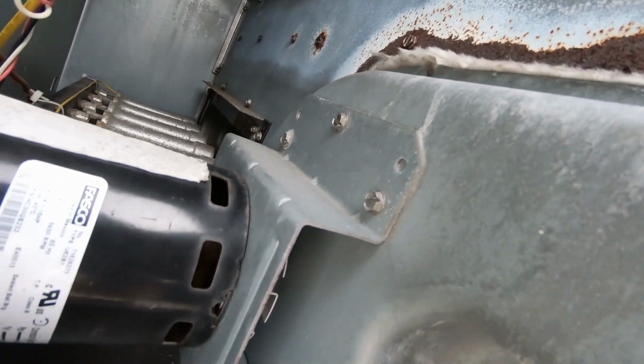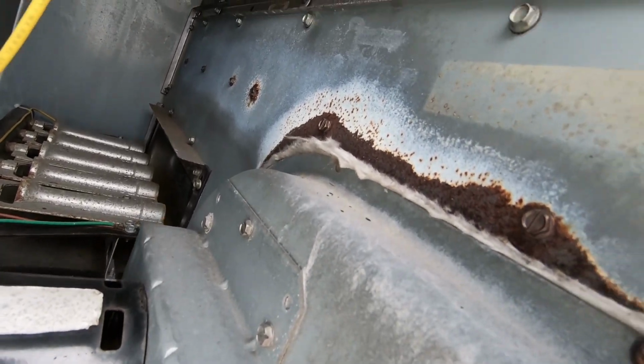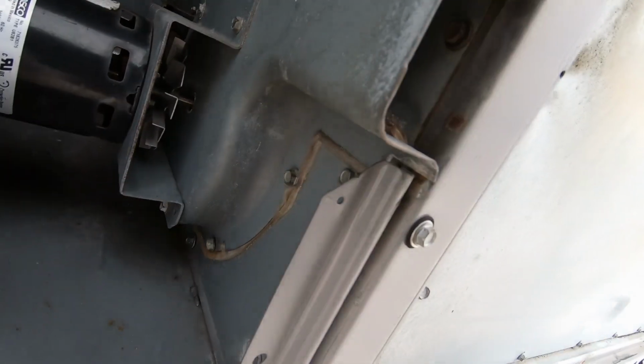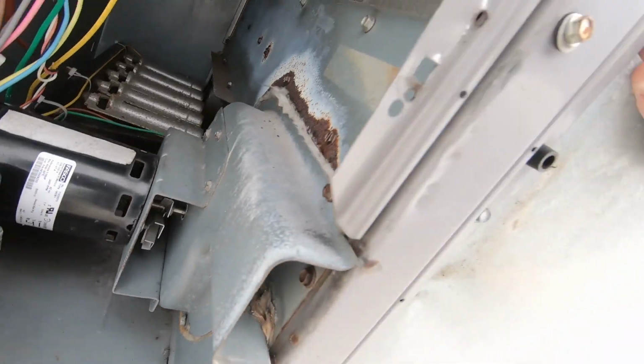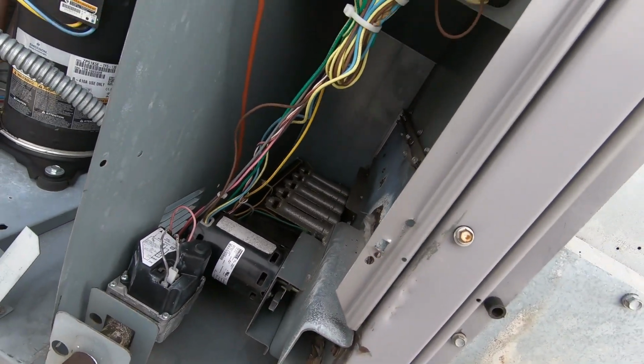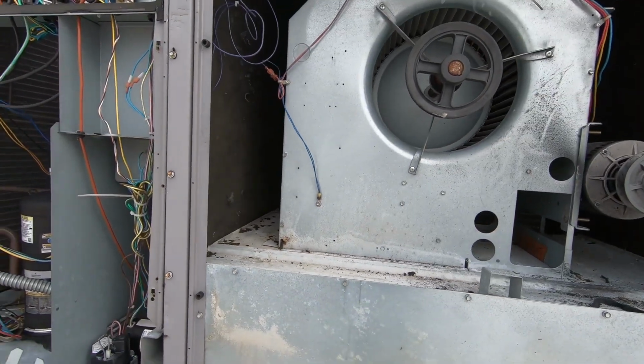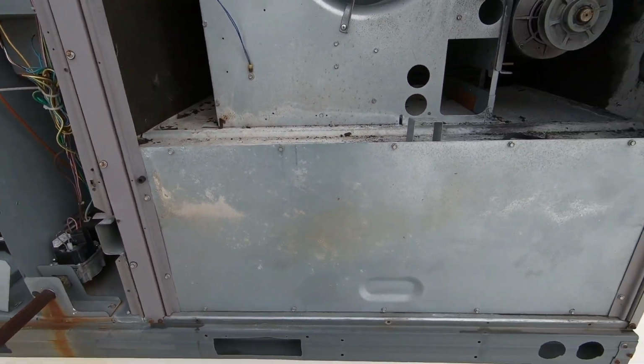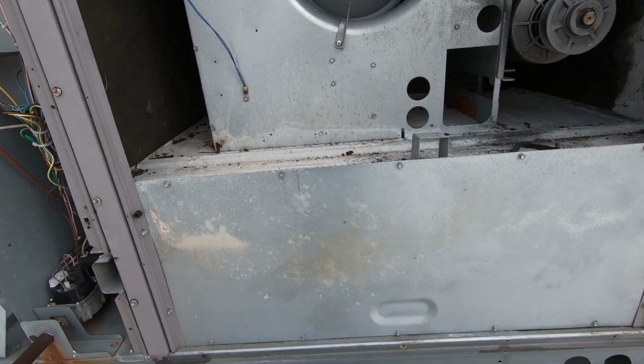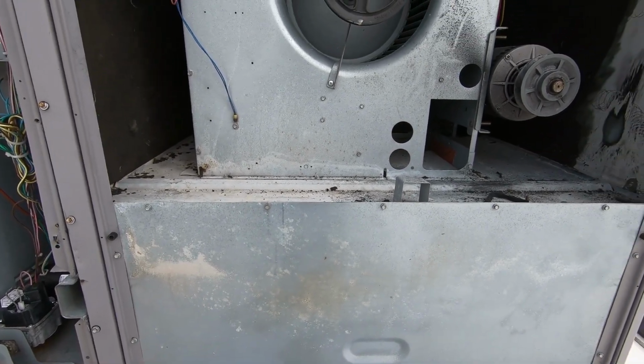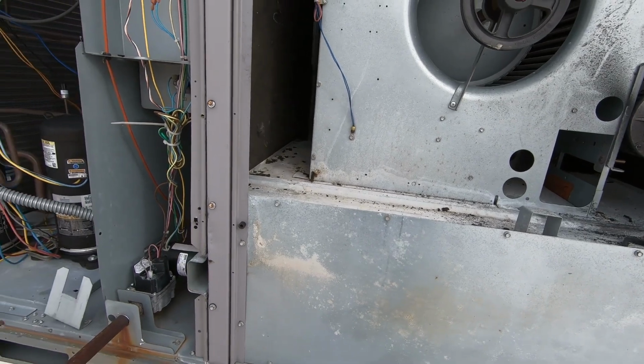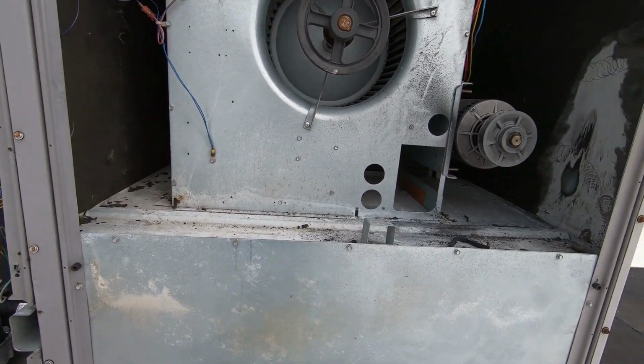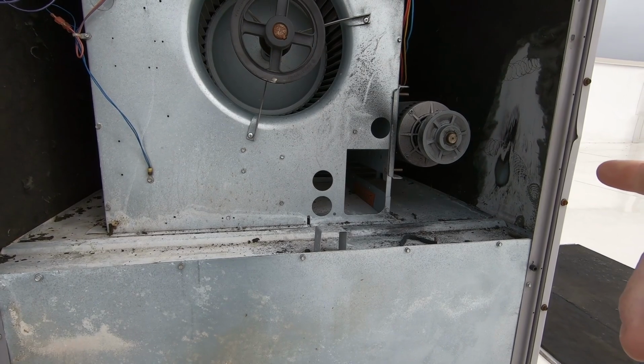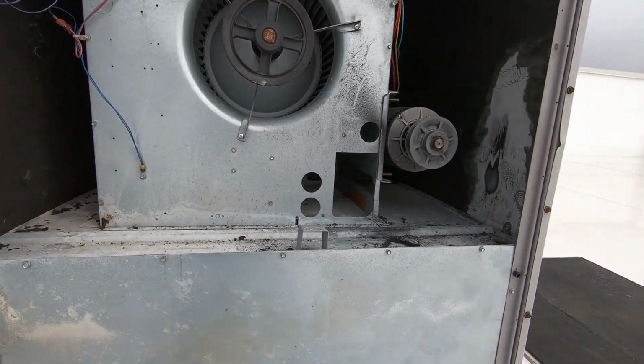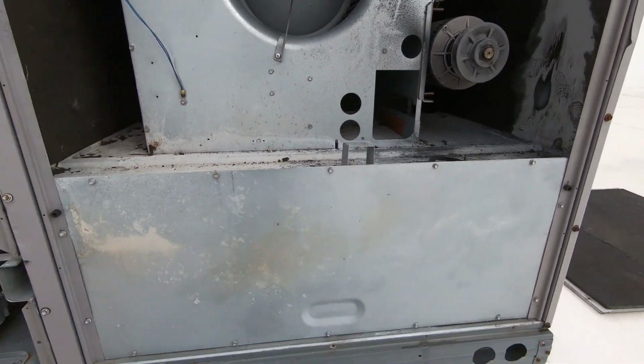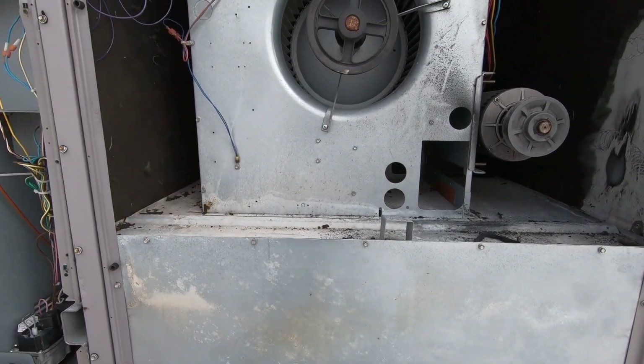Front plate has some wear to it. Some of the screws are halfway out. I can't tell if this thing's been replaced before or not. Let me pull this, get a good look at the heat exchanger. That's really going to determine whether or not we cycle it any further to see if it's a motor. I'm going to test it electrically, but I'm a little leery to power it up, go from there. But let me go ahead and inspect this, and I'll bring you along.